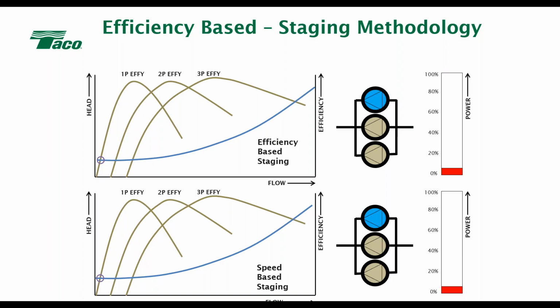So how do we maintain best efficiency? If I look at what's been industry standard for years and years and years, it is speed-based staging. The problem with speed-based staging is it's simple, and you cross over the best efficiency points in a pump's operating curve. Speed-based staging is just that: I get a pump, I ramp it all the way up to 90 or 100%, and then I turn the second pump on. When the second pump gets all the way up, then I turn the third one on. And that is speed-based staging.